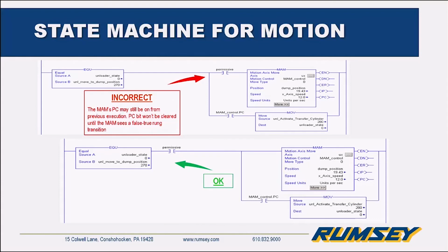When doing motion, because of this phenomenon that from the previous execution some bits could be maintained, it would be incorrect to set up your logic as is shown in the first screenshot. Yes, I'm in the state. The permissive may not be true when I get there, and I may have a PC bit, a process complete bit, set from the previous execution. So what would happen if this is not ready? I would just blow through it, never do this action, and move on to the next state.